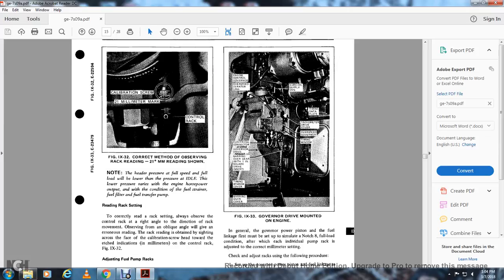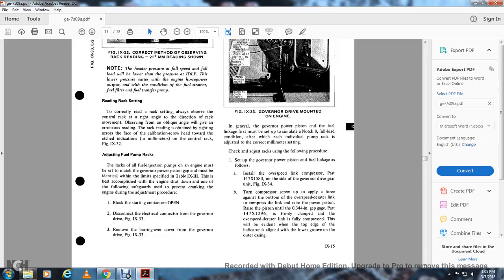Move the bearing over cover of the governor drive (figure 9-33). Figure 9-33 shows the governor drive mounted on the engine, with the engine control governor, overspeed deraider link, lube oil supply pipe, timing data plate, tachometer drive, cover, overspeed governor, timing window, electrical connector, governor drive barrel bearing, bearing over gear, and bearing over cover. In general, the governor power piston fuel linkage must first be set to simulate the notch 8 full load condition, after which individual pump rack adjustments are made. To set up the governor power piston fuel injection, install the overspeed link compressor, part 147X1580, on the side of the governor drive gear (figure 9-34). Turn the compressor screw to apply force against the bottom of the overspeed deraider link.